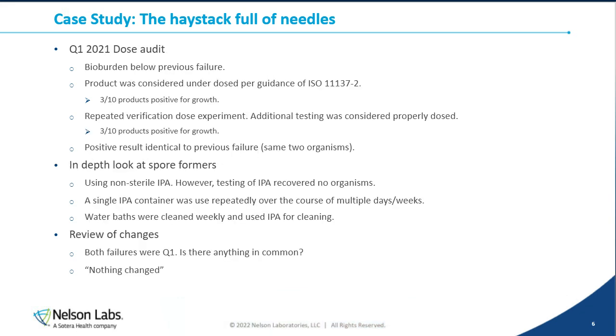However, the next dose audit came along and it was, again, below the previous bioburden. It was actually even below the previous failure. We saw a reduction in bioburden compared to what we had even seen. However, the product was considered underdosed. So with underdosed product, there is the option to proceed with your dose audit at risk. We did so at their direction, and there were 3 out of 10 positives for the test of sterility, which is an automatic failure for the dose audit.